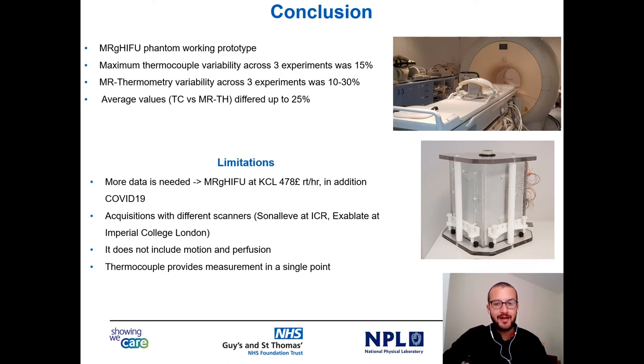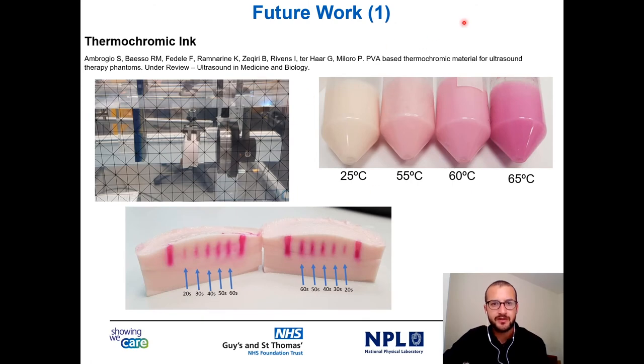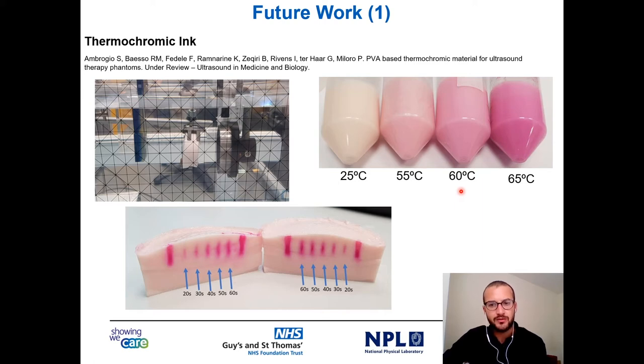Thermocouple provides measurement in a single point — this is a major limitation. However, we are already moving forward and we got a grant to develop a thin film matrix array sensor for temperature distribution measurements. In addition, we have a paper under review in Ultrasound in Medicine and Biology for the development of a PVA-based thermochromic material. This material changes colour in relation to temperature in the region of interest of HIFU, and can be embedded in phantoms or in 3D models.